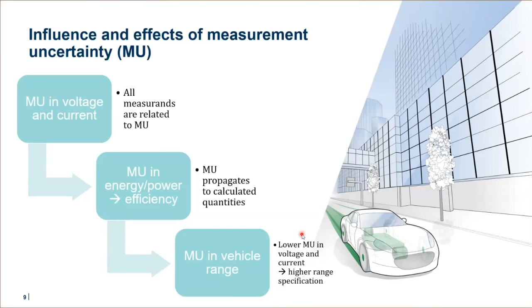Now, to go to the analysis and how to evaluate measurement uncertainty, I want to again distinguish between different error effects. In this context, I distinguish between two groups: systematic error effects on the one hand, and these errors are characterized by the fact that they are reproducible if I repeat a measurement, in the first step under equal environmental conditions, but also, of course, with the same operating point. And then, since we can reproduce these error effects by following measurements, they are generally avoidable by compensation. And if we talk about measurement, this means calibration.